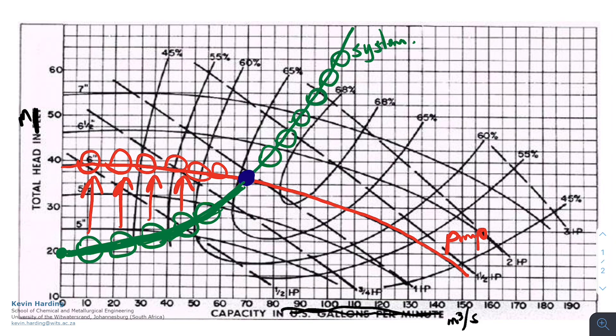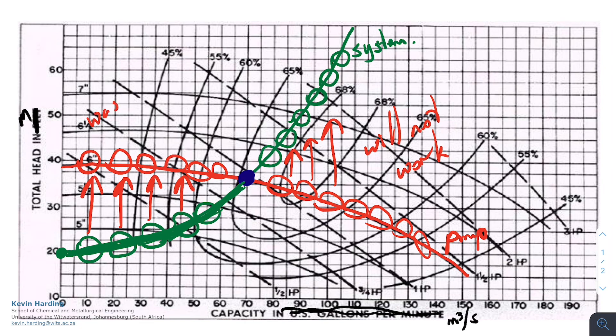Similarly, if we look at the section above the intercept, we now have the circles that I've got in the green versus the red circles that the pump is giving us. We can again, by this graph, see that we are able to get a pump that delivers the flow rate, but the pump is now not able to give, it's not giving us enough head. So this system will not work. So above the intercept, the system will not work. Below this intercept, we are wasting energy.